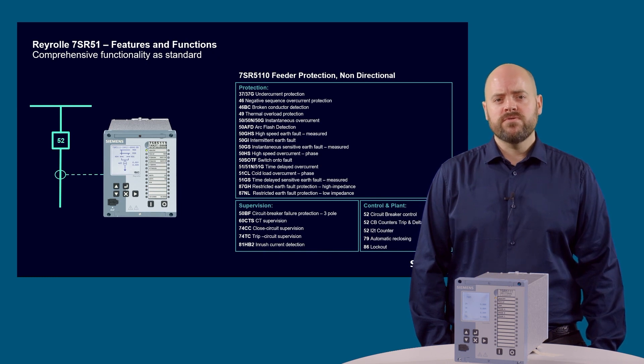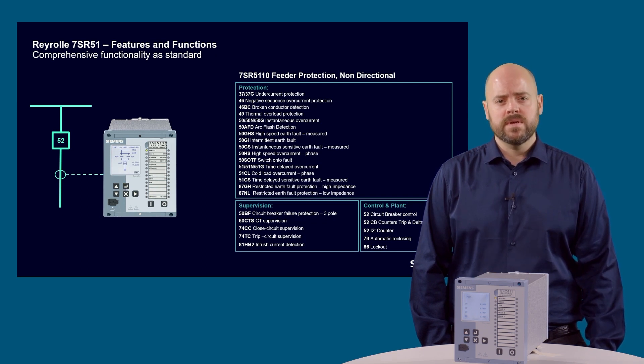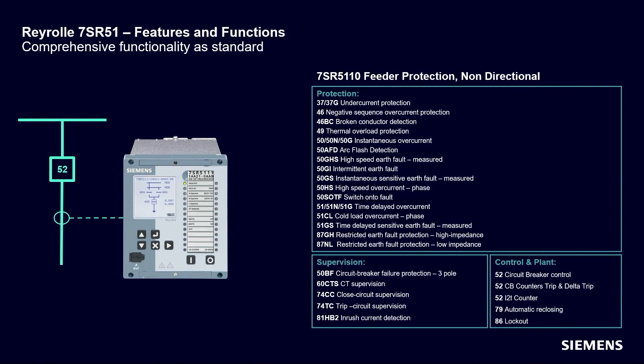Its 4CT inputs are suitable for connection to both 1A and 5A current transformer secondary windings and includes a core range of functions as standard. Instantaneous and time-delayed overcurrent protection functions 50 and 51 provide 3-phase overcurrent and both calculated earth fault — determined from the sum of the 3-phase currents using suffix N after the function number — and measured earth fault protection, directly measured from a neutral CT or residual connection of the 3 line CTs, using suffix G.